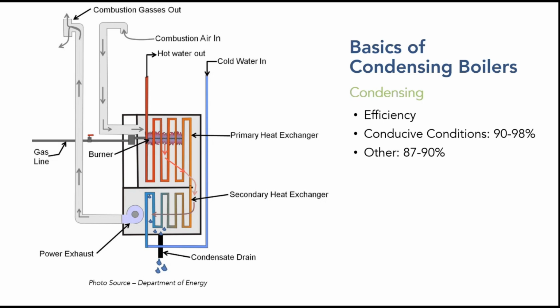This is a second view, and the takeaway here is the same concept. This is more of a wall-mounted instant hot water heater kind of configuration. But what I wanted to point out on this, from the Department of Energy, a diagram they had, is that there's often a secondary heat exchanger. So you have your primary heat exchanger, which is basically your conventional style heat transfer, and then your secondary heat exchanger where you start getting your condensate coming out of your flue gas.